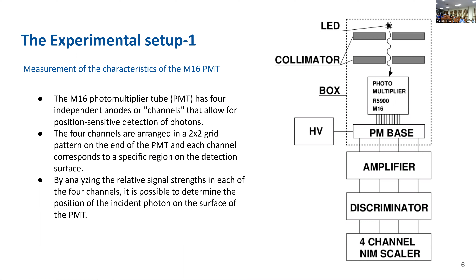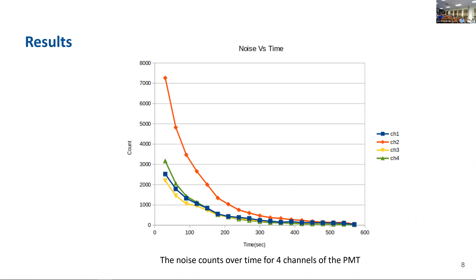And this is the result of the first experiment. First, we measured the noise counts that are passing in the detector over time. The reason for this is that when we first turn on the high voltage, there are some transition effects that cause additional noise, and in addition to that, there could be some additional light left in the box. So we waited for some time and got the results, and as you can see, the noise levels gradually decreased over time, so we can work with that multiplier.